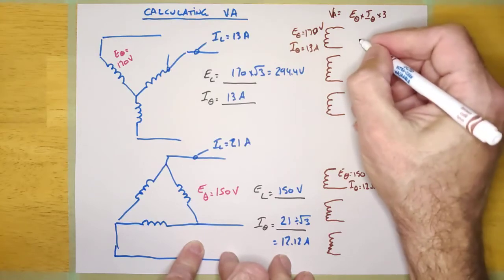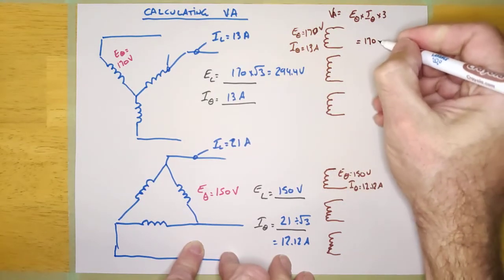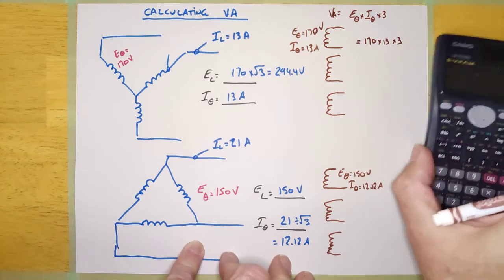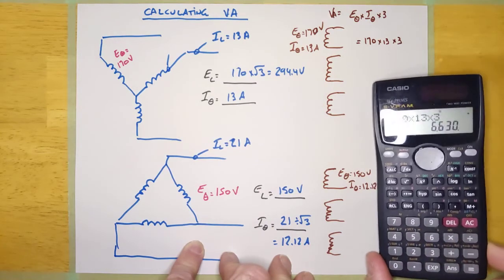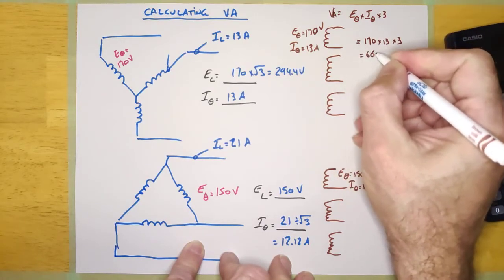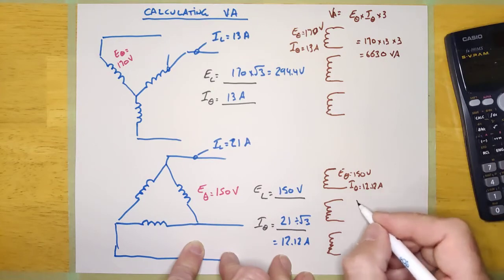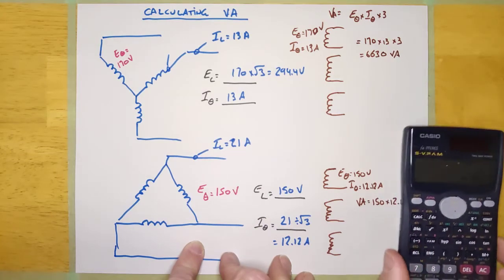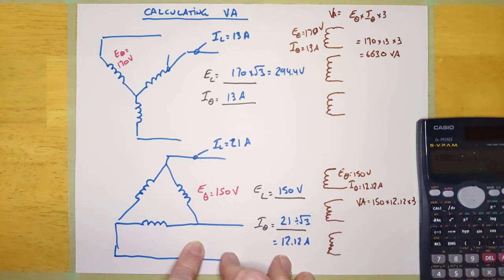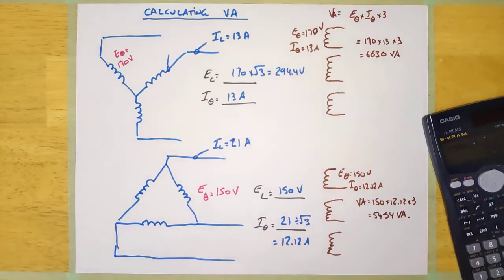For the Y system, it's going to be 170 times 13 times 3 — that gives us 6,630 VA. And for the Delta system, the VA will be 150 times 12.12 times 3, which equals 5,454 VA. That formula will always work, but it's not the handiest formula in the world.